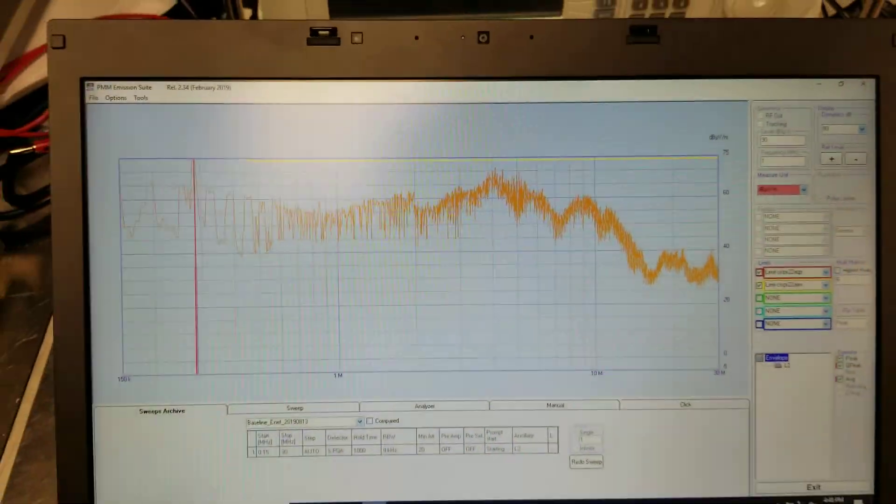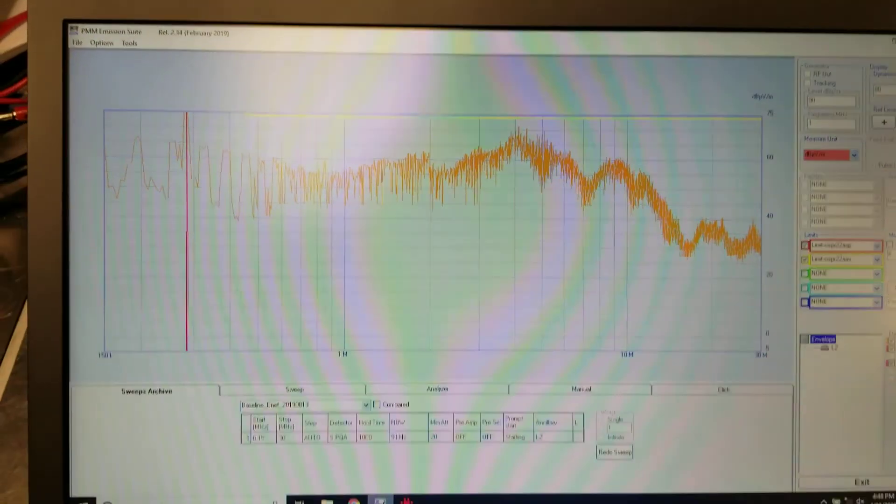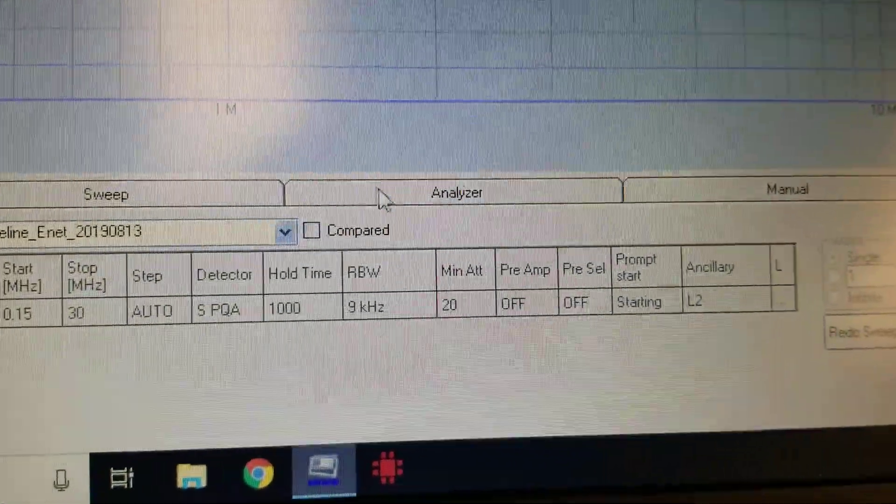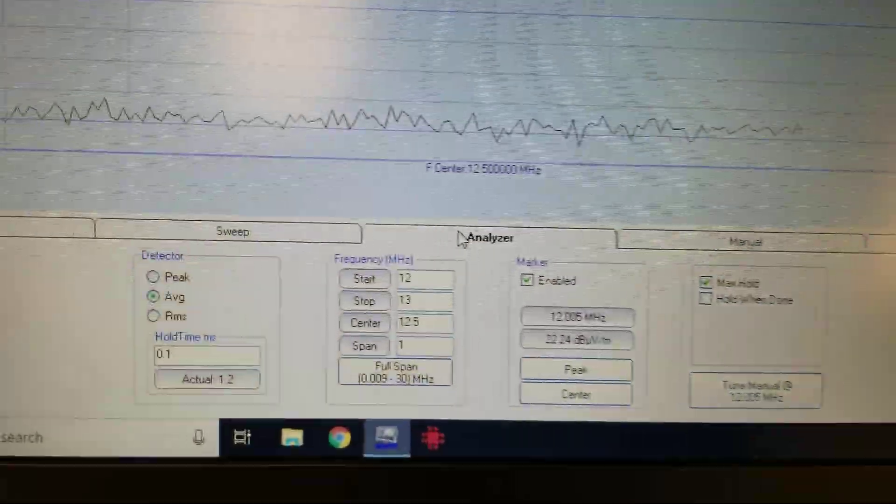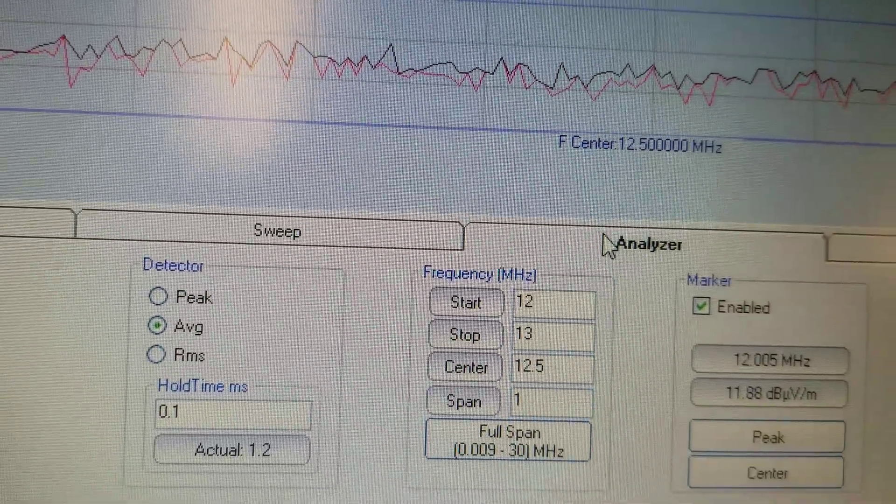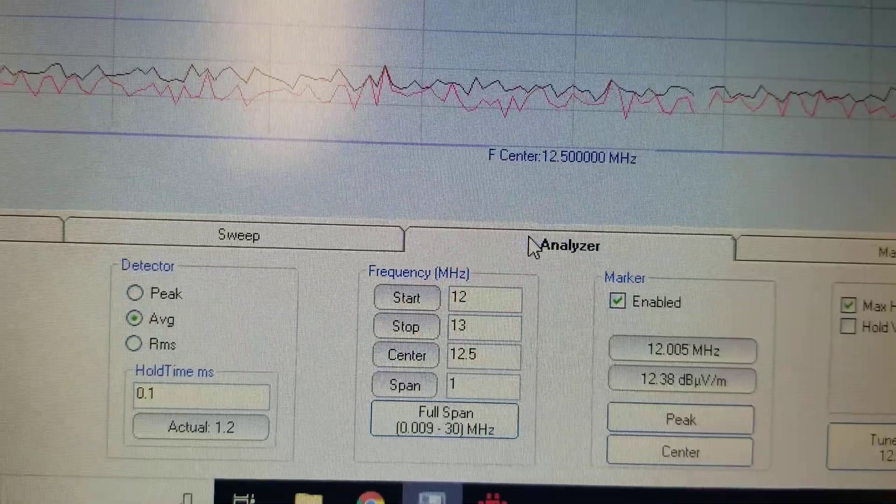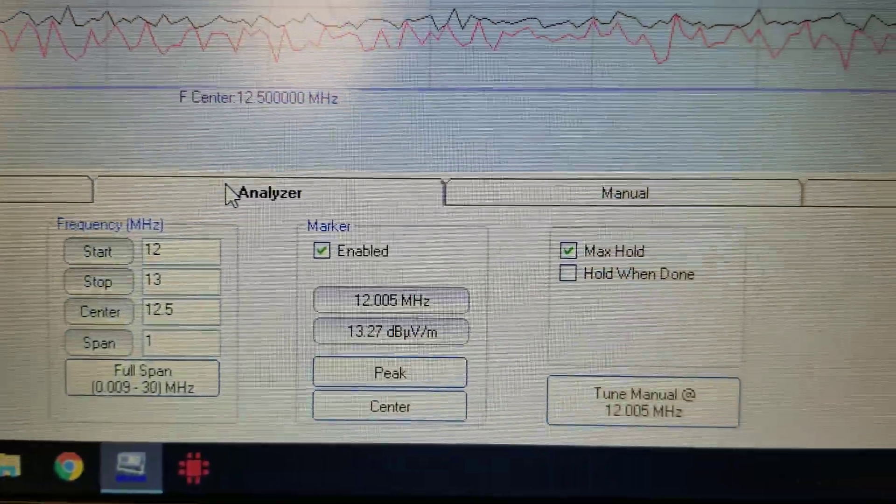Once the suite is initialized for the PMM 7010, we're going to use the analyzer tab, which will bring up all of the settings that have been pre-configured before, such as the start frequency, stop frequency, center frequency, the span, your detectors looking for peak, average RMS voltage, and whether you want max hold or hold when done.